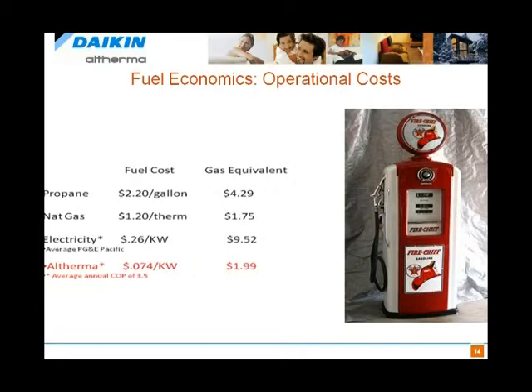You can see that with the altherma, using a COP of 3.5 -- dividing the COP into the cost of electricity -- you're at about $2 an equivalent gallon. So you're substantially below propane, and you may be at or a little more than natural gas. This can be studied in more depth, but the point is to give a general orientation on the economics out there.